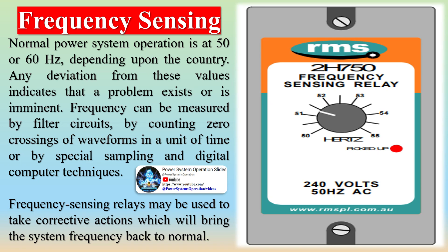Frequency can be measured by filter circuits, by counting zero crossings of waveforms in a unit of time, or by special sampling and digital computer techniques. Frequency sensing relays may be used to take corrective actions which will bring the system frequency back to normal.